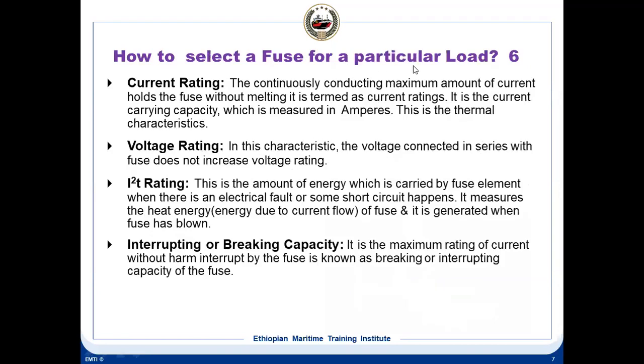How do you select a fuse for a particular load? Suppose on board ship you find the fuse is blown, and you don't have an appropriate fuse to replace it. So how do you select it? First thing is the current has to be the same, because if you put higher amps, you are damaging the equipment. If you put lower amps, this will blow off very early.